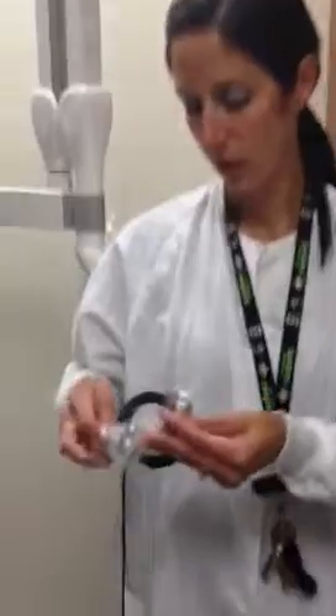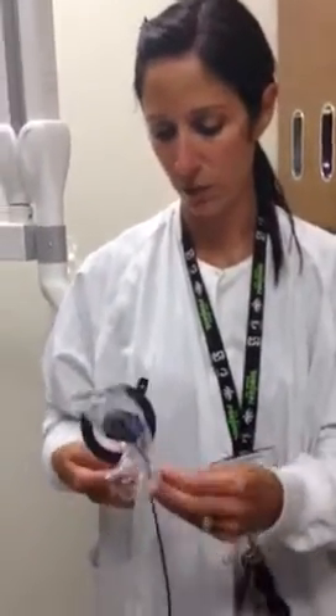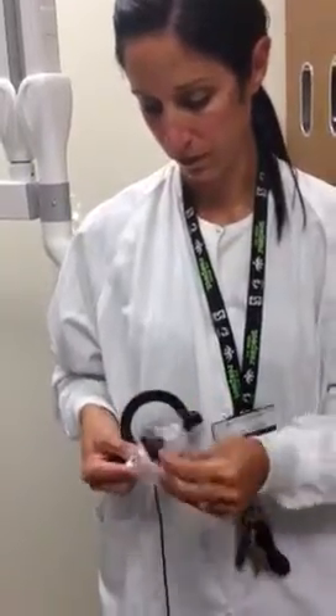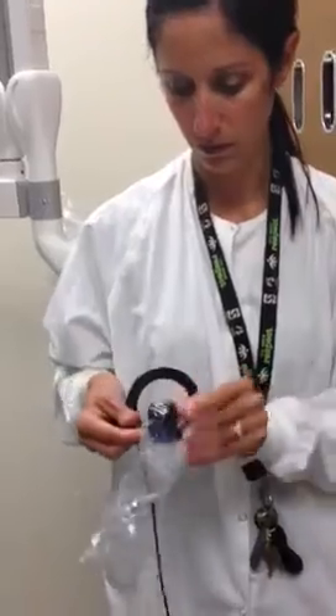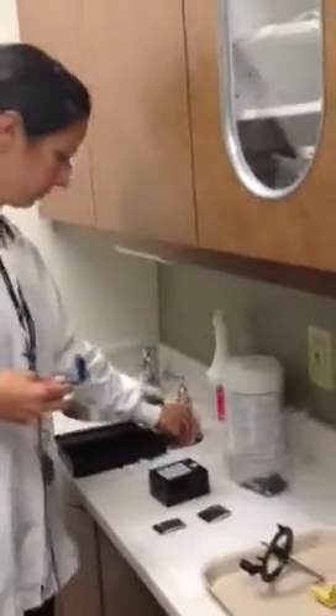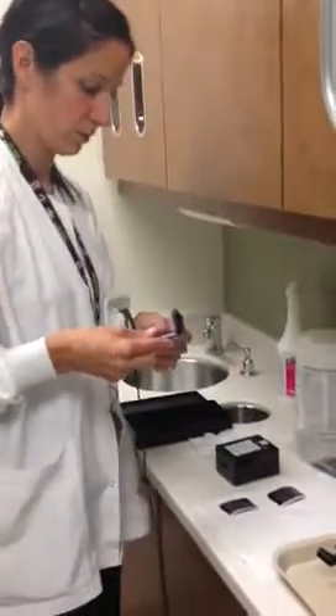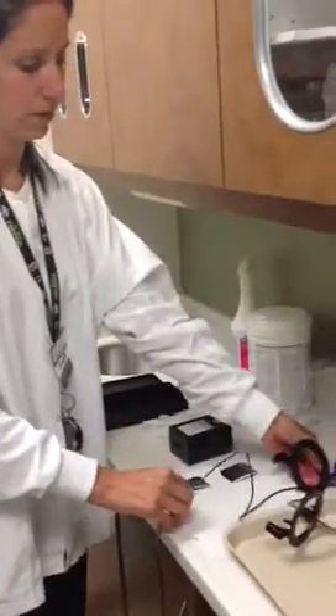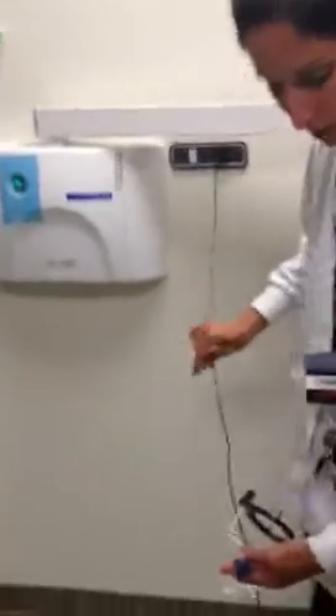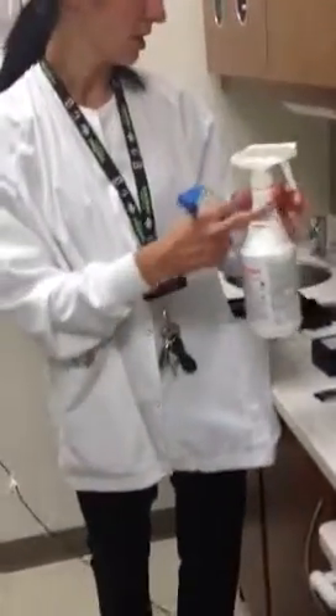Now to disinfect the holders with gloved hands, obviously you would remove the barrier. And you would take off your contaminated gloves, remove the sensor, place it back up on the hook so that it's not going to get damaged. Okay. And these do not get sterilized, so they get sprayed down with Cavicide. You can't use the wipes. These wipes actually will start to disintegrate the plastic.